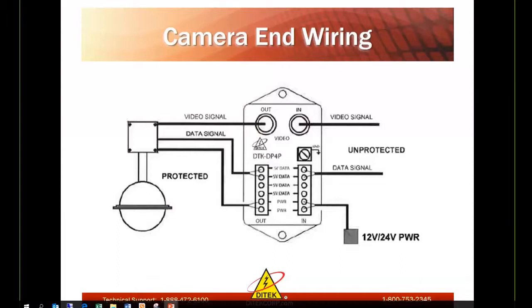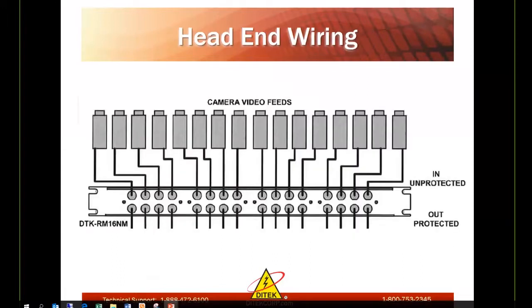Here's a camera end wiring that we do. That would be the DP4P, that's for the pan-tilt-zoom cameras. It protects the video signal in and out, and as you notice, the unprotected and the protected are all on the same side, whether it be video, data, or power. We offer the 2-pair on that, again, and the low-volt power. At the head-end equipment, the RM16NM, we're offering the product to protect the separate video feeds coming from an analog camera back to your head-end device to protect your DVR. And it is a single-point ground device with 1U spacing.